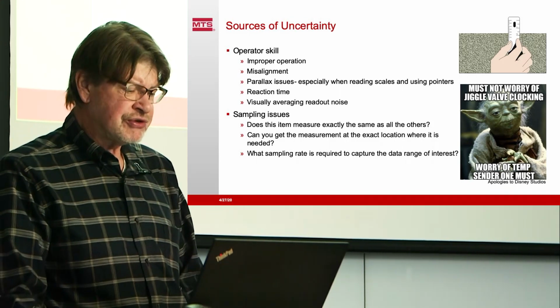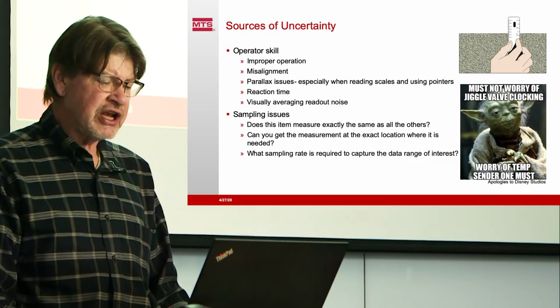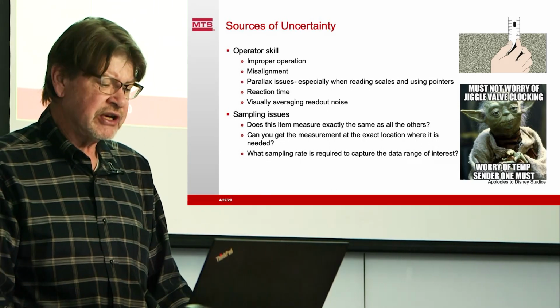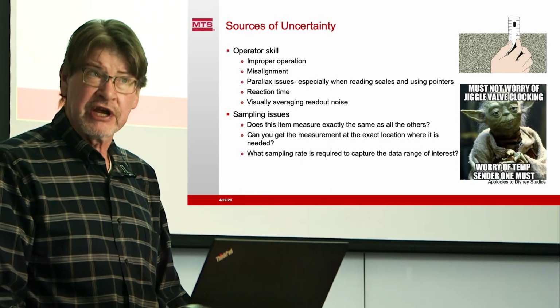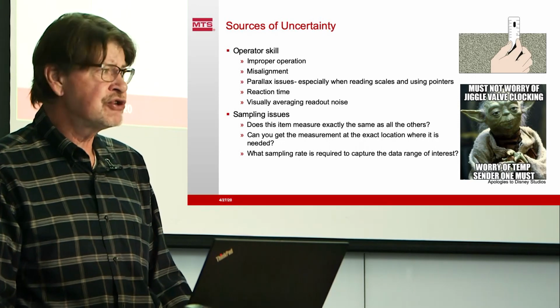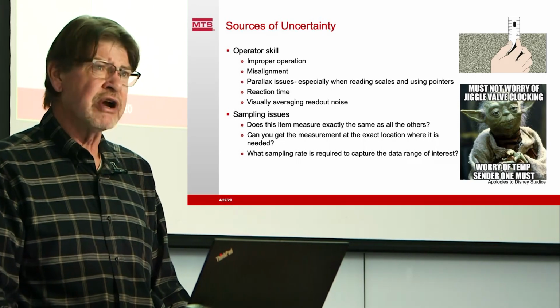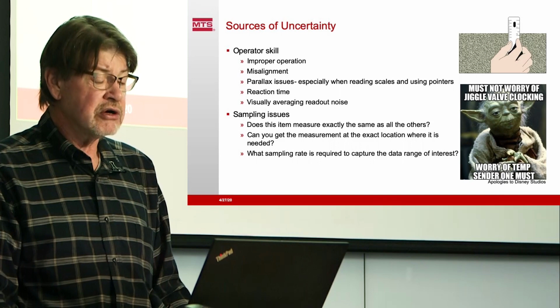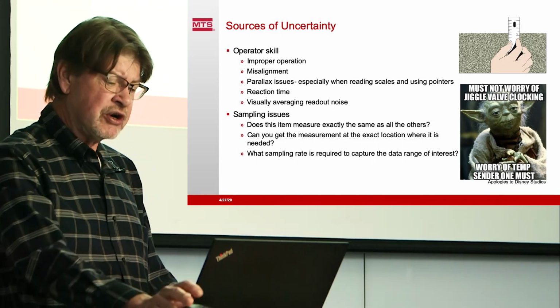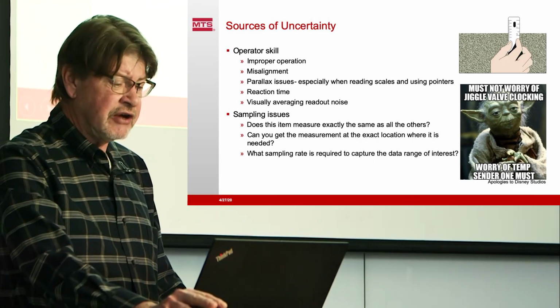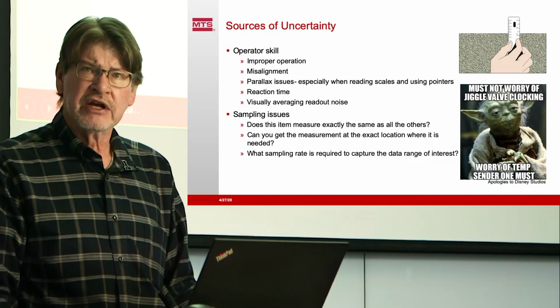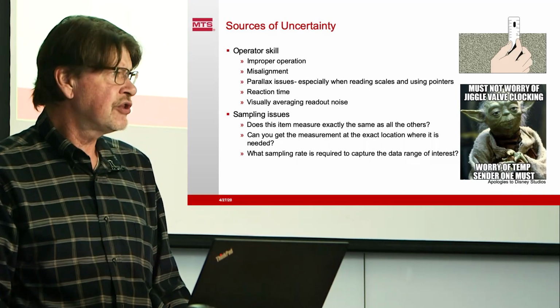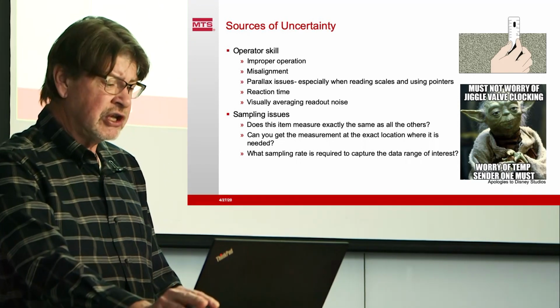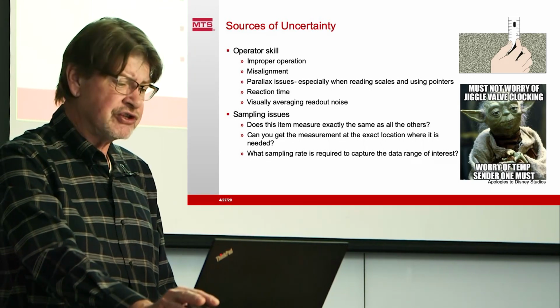Sampling issues. Does this item measure exactly the same as all the others? Can you get the measurement at exactly the location where it is needed? The example we had with the LVDT and the piston rod was one of those where I can't measure right where I want to. There will be errors then. What sampling rate is required to catch the range of interest? You have to know something about digital data and conditioning it, working with Nyquist and things before you can make intelligent decisions about your sample rates and requirements.